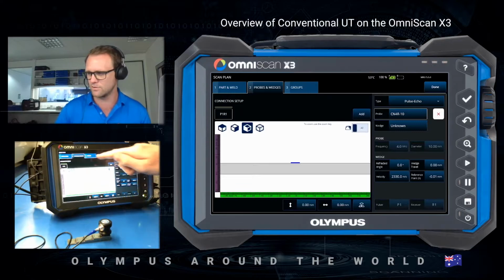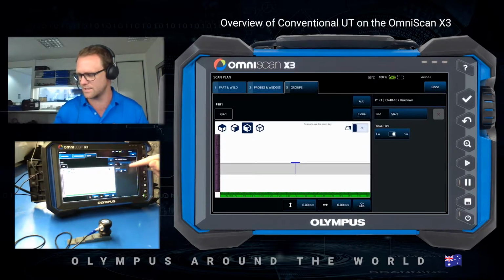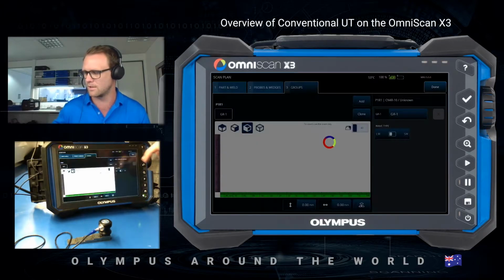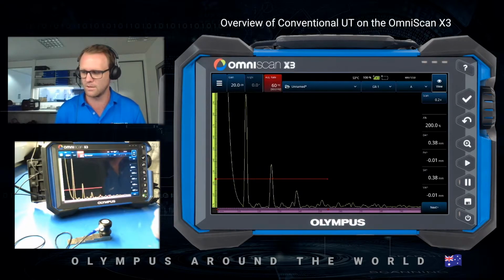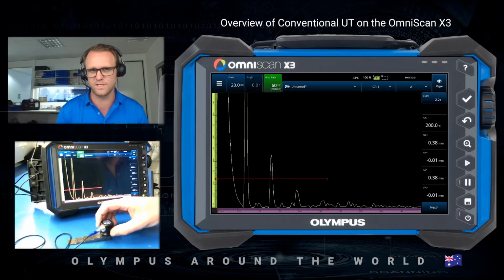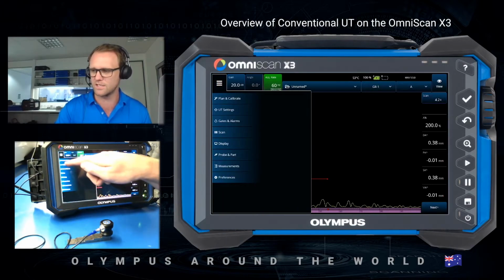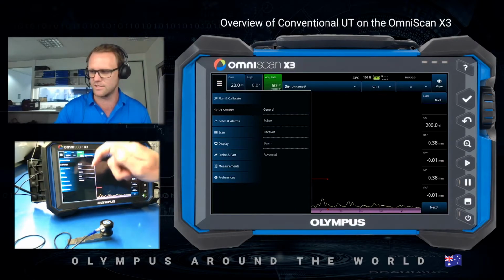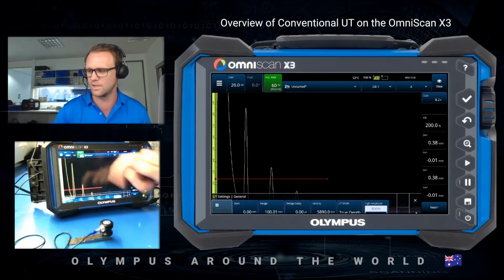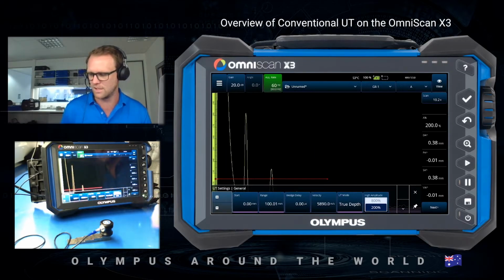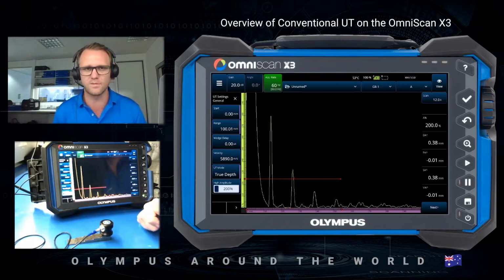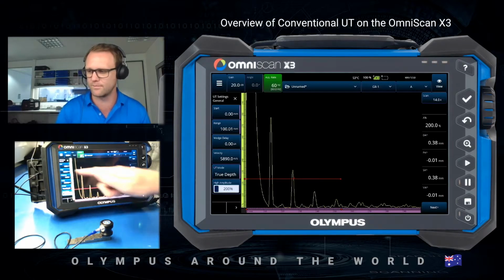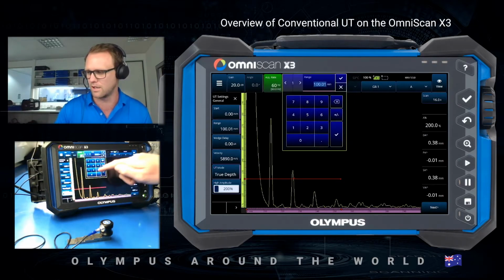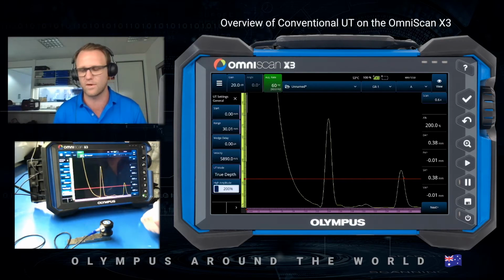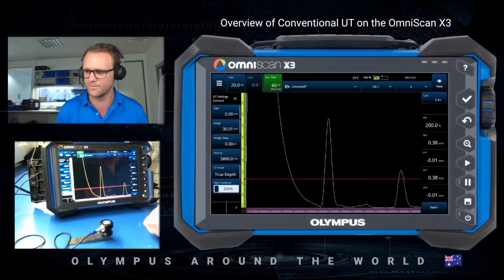And then I can go into groups. Within groups, I just need to change it to longitudinal wave so it sets the suitable velocity, and then done. So now we have a basic UT set. To make changes, as you would in a UT set, I press the UT settings within the burger menu. Press General first. From here, I like to pin it, so it feels a bit more familiar as a UT set. I can change my range. I'm going to set it to 30, so it's within range of my 12.5mm step block.